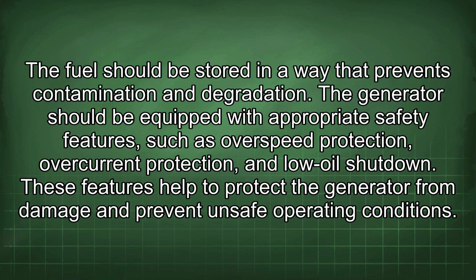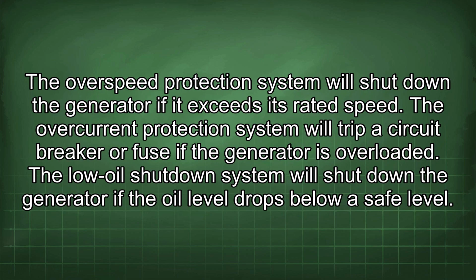The generator should be equipped with appropriate safety features such as overspeed protection, overcurrent protection, and low oil shutdown. These features help to protect the generator from damage and prevent unsafe operating conditions. The overspeed protection system will shut down the generator if it exceeds its rated speed. The overcurrent protection system will trip a circuit breaker or fuse if the generator is overloaded. The low oil shutdown system will shut down the generator if the oil level drops below a safe level.